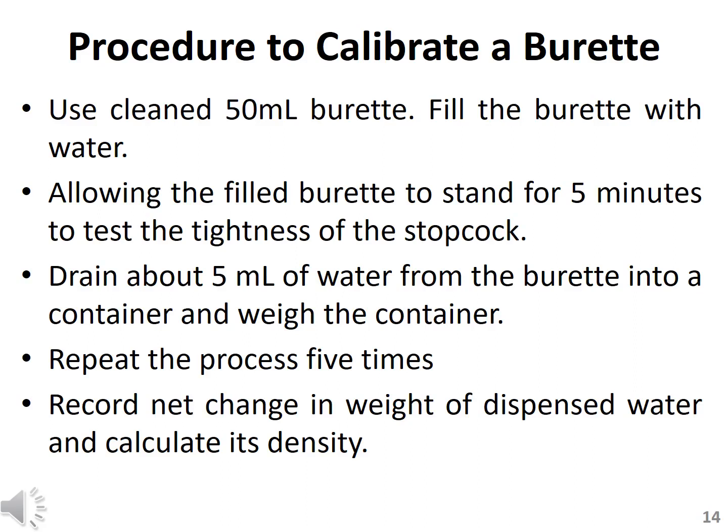After this, test the tightness of the stopcock, which is used to control the flow of the titrant. The tightness of the stopcock will be checked by allowing the burette to stand for 5 minutes. We will wait for 5 minutes to observe if there is any drop coming from the bottom of the burette. During this 5 minutes, there must be no considerable change in the volume of the titrant which is in the burette.